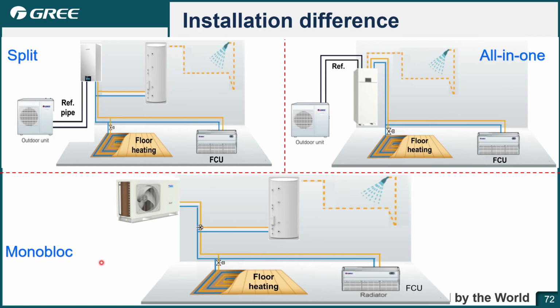Then the monoblock. For the monoblock, you can see no need to install the refrigerant pipe, no copper pipe, just connect the water pipe to the other units, in and out. And the three-way valve is an external three-way valve, so you need to install it by yourself on the water pipe. For the other parts, they are the same.